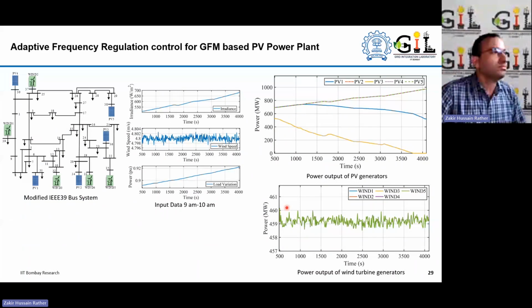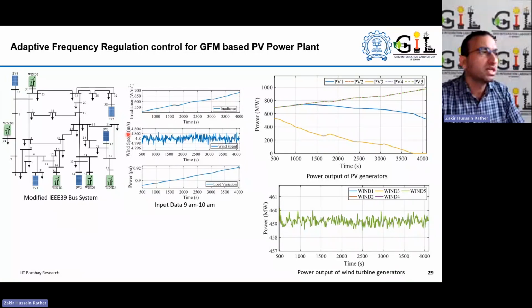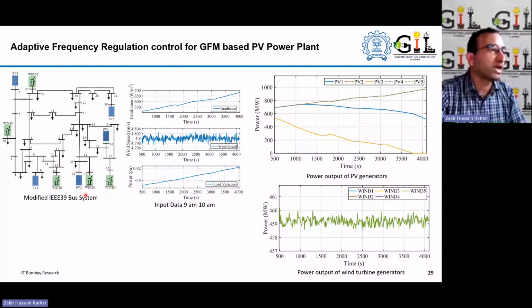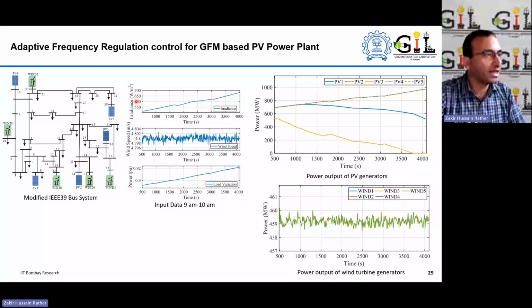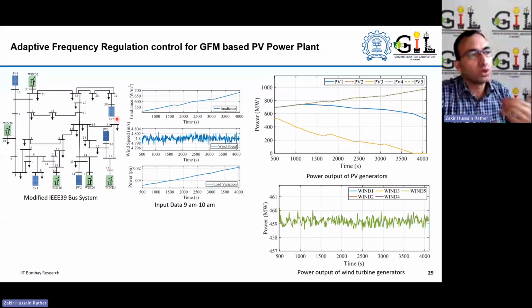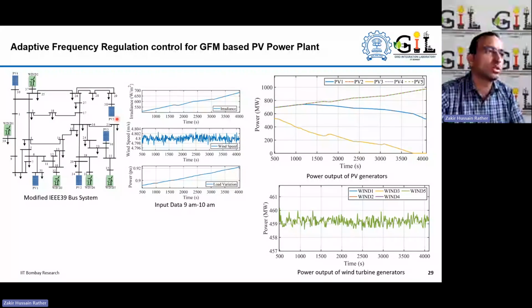Similarly, this is another study we carried out. In this case, it is more of a system level frequency control in terms of the reserves and other frequency support. This is again the same system, 100% IBR based penetration, and here we have a mix of solar PV and wind power plants in the system. The irradiance is variable and the load is variable to look at more realistic scenarios.